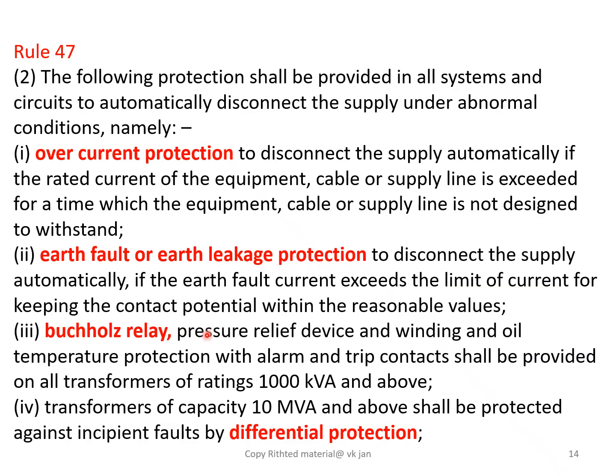pressure relief device, and winding and oil temperature protection with alarm and trip contacts shall be provided on all transformers of rating 1000 kVA and above. Transformers of capacity 10 MVA and above shall be protected against incipient fault by differential protections.